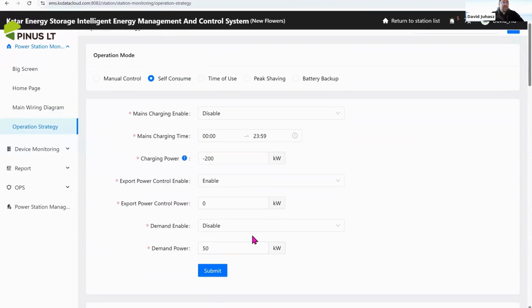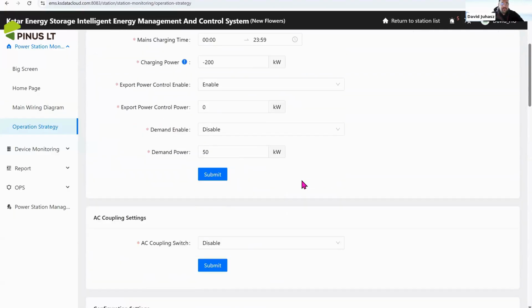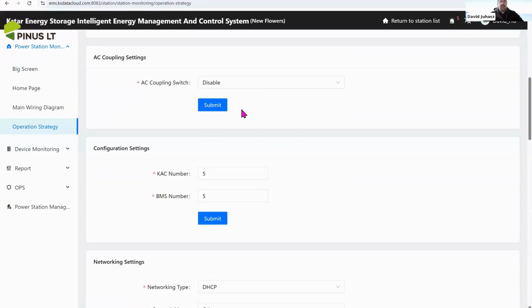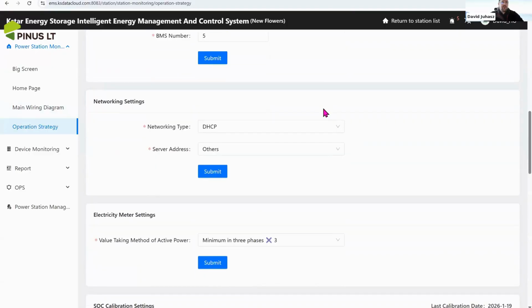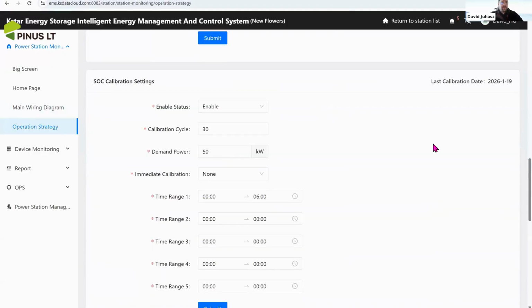Demand power means the maximum power that can come from the AC grid connection point to the batteries. The maximum charging power, we can limit when to charge the batteries, and we can set if there is another AC coupled inverter on that same bus bar. We can set the enable, and it makes it smoother operation together with KSTAR inverters.